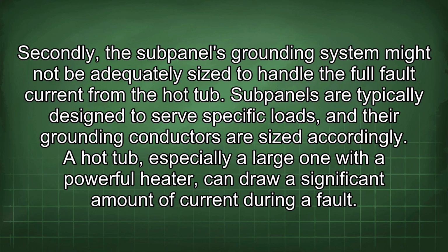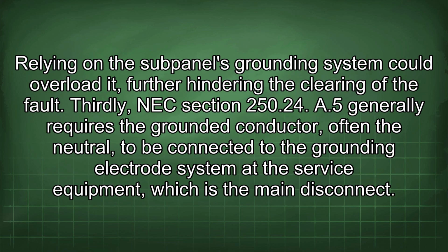A hot tub, especially a large one with a powerful heater, can draw a significant amount of current during a fault. Relying on the subpanel's grounding system could overload it, further hindering the clearing of the fault. Thirdly, NEC section 250.24(A)(5) generally requires the grounded conductor, often the neutral, to be connected to the grounding electrode system at the service equipment, which is the main disconnect.